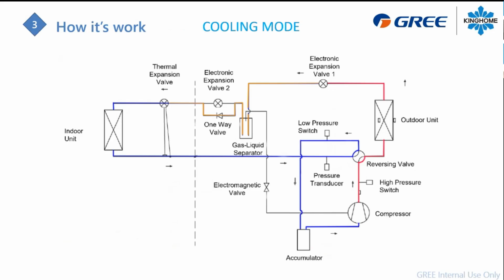So for this kind of unit, you will have your compressor right here. The compressor will take your low pressure gas and compress it to a high pressure, high temperature refrigerant. So directly from the discharge line right here, we're gonna pass in the reversing valve. In that scenario, we are in cooling mode, just to be aware of it. The reversing valve manages the flow of the refrigerant if we are in cooling mode or in heating mode. Now we are in cooling mode, so the reversing valve is not energized. Okay, 0 volt here on the reversing valve. So it's gonna flow through the reversing valve and go to the outdoor unit, your condenser.